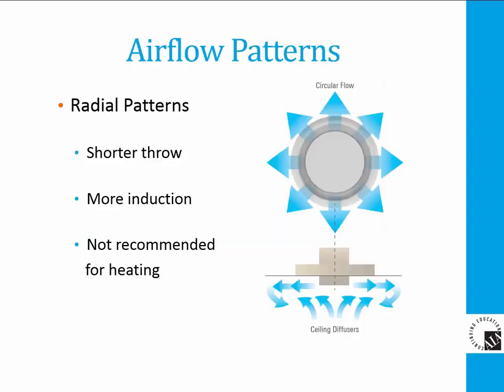There are two basic types of airflow patterns. First, we will look at a circular flow air pattern, sometimes called a radial air pattern. When air is discharged from an outlet and distributed evenly in all directions, it is known as a radial air pattern. Since air is discharged evenly in all directions, the result is that it travels a shorter distance from the center of the outlet to a given terminal velocity, let's say 50 feet per minute.